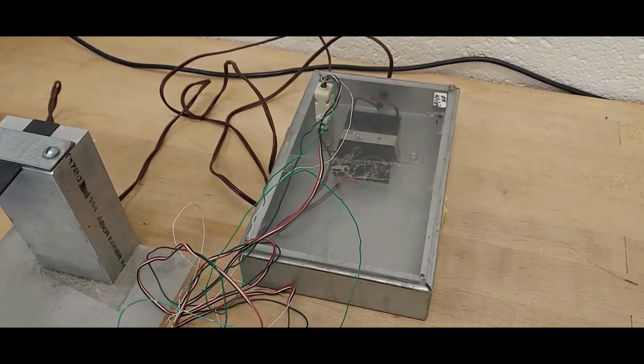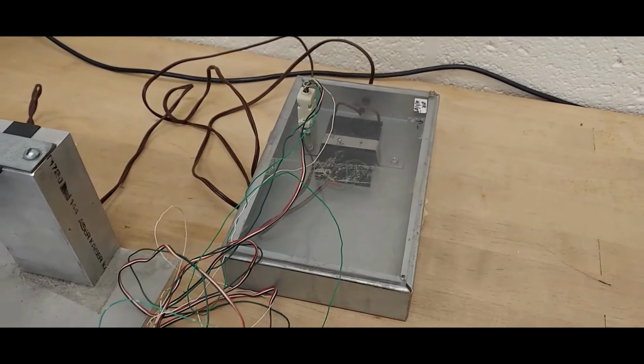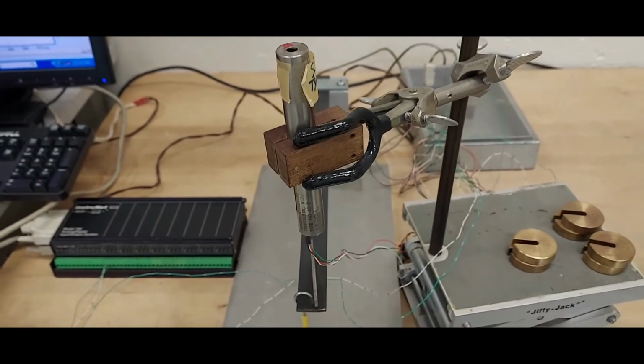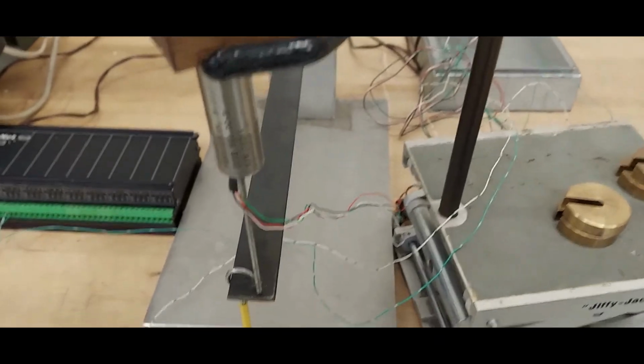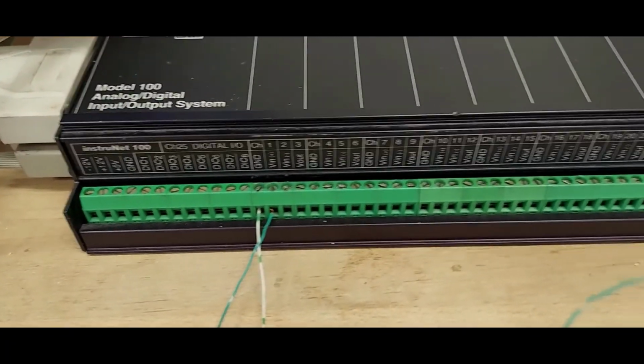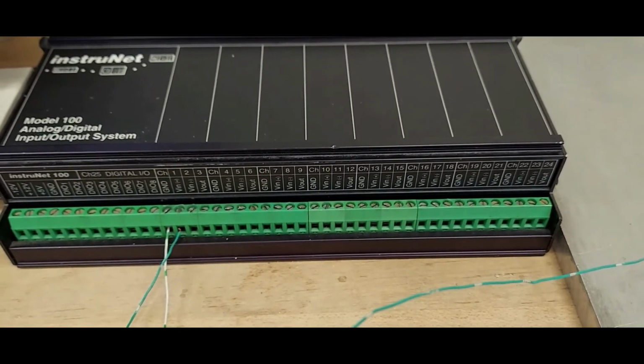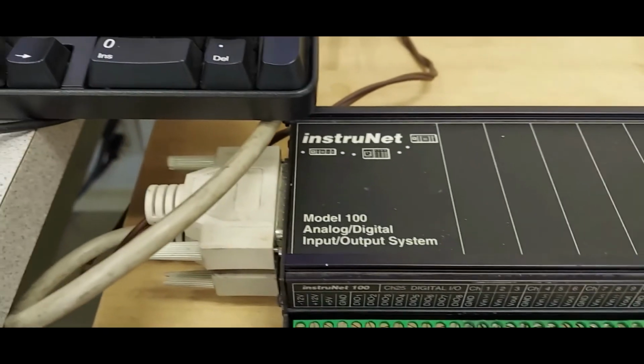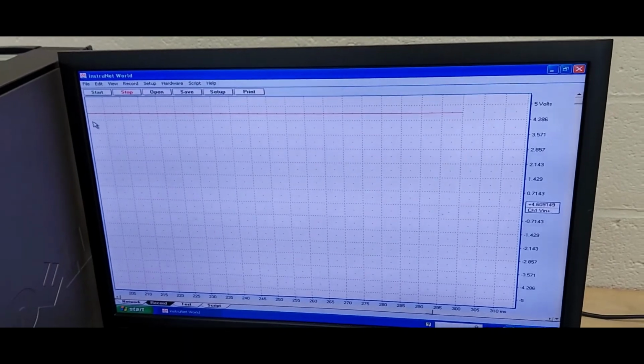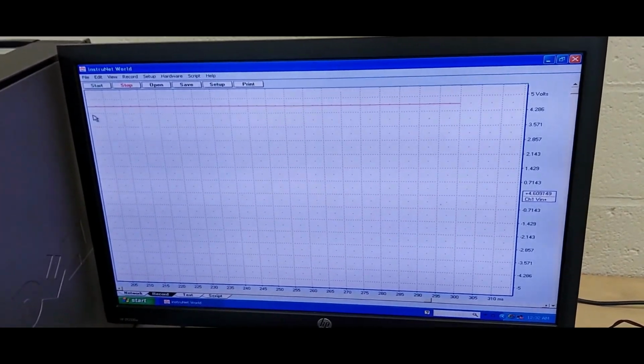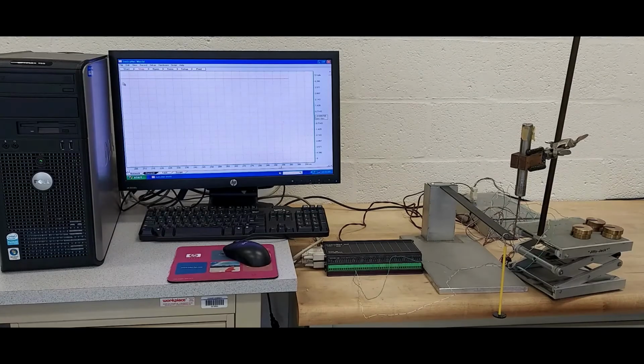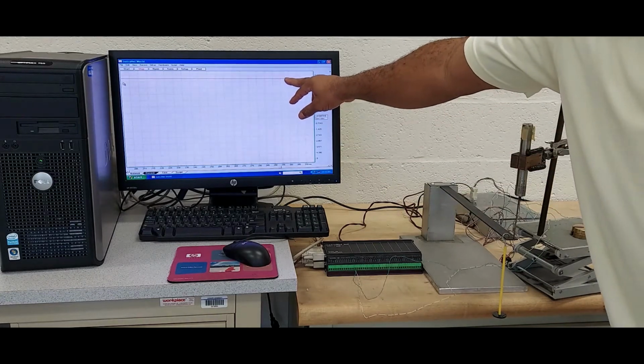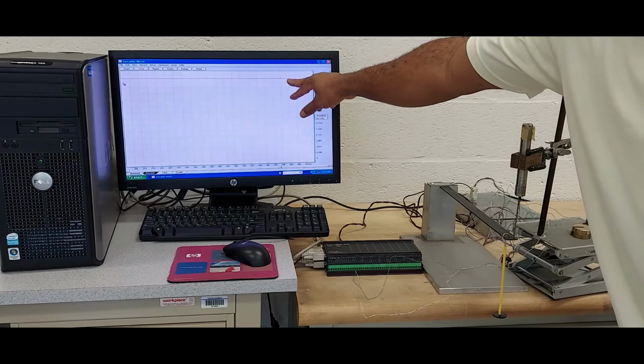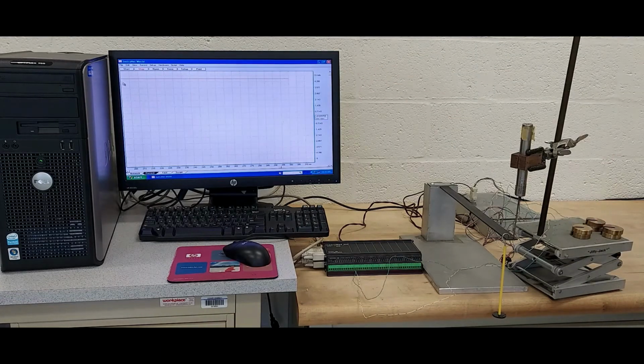So this is a close-up of the power supply, which supplies AC power to the LVDT, and the LVDT is then connected to our InstruNet data acquisition system, and our acquisition system is then connected to our CPU, which gives us our voltage output reading on the software. Now that the system is configured and we have already recorded our 0 value, and this red line indicates our 0 value, we will begin by applying our first load.